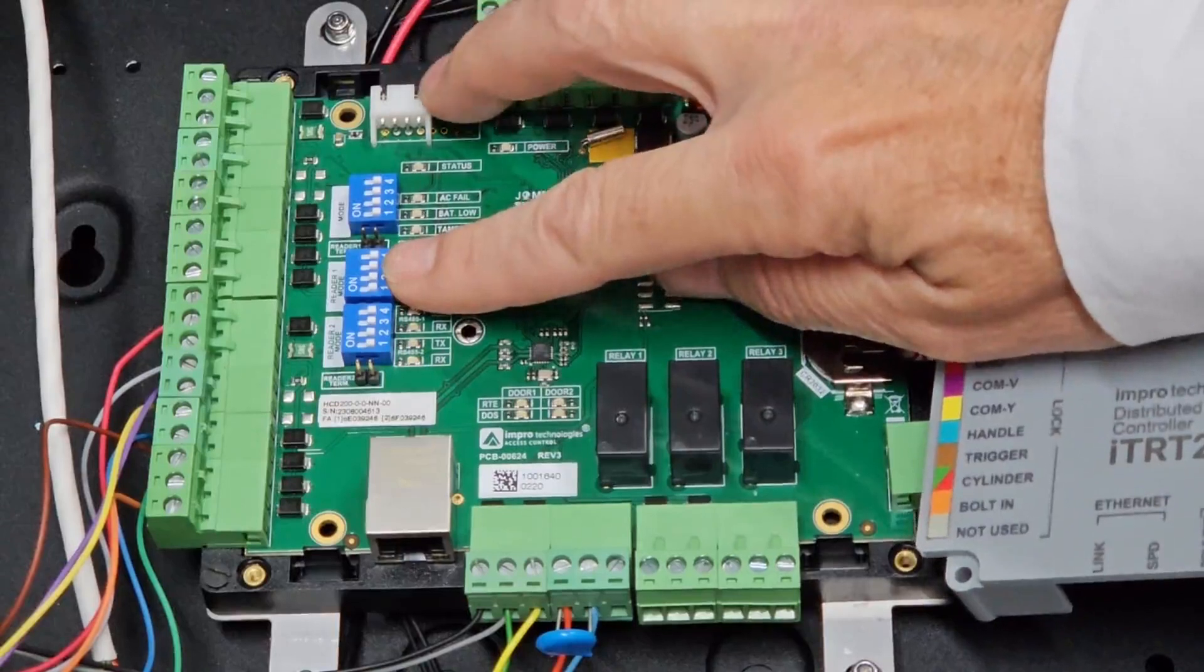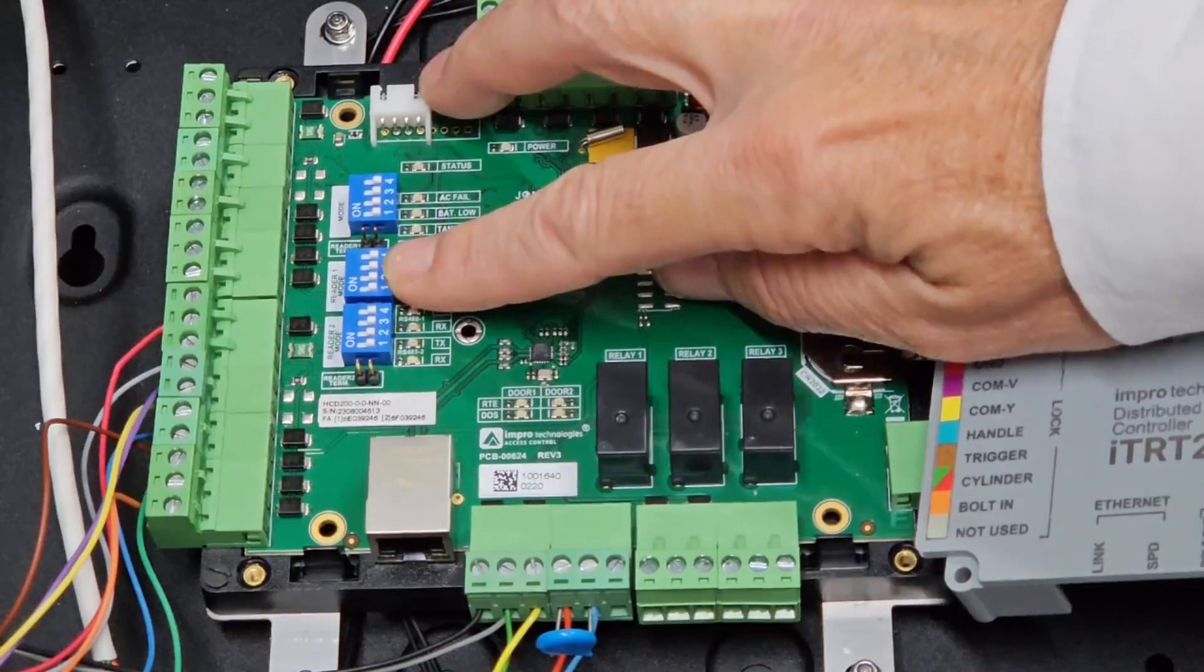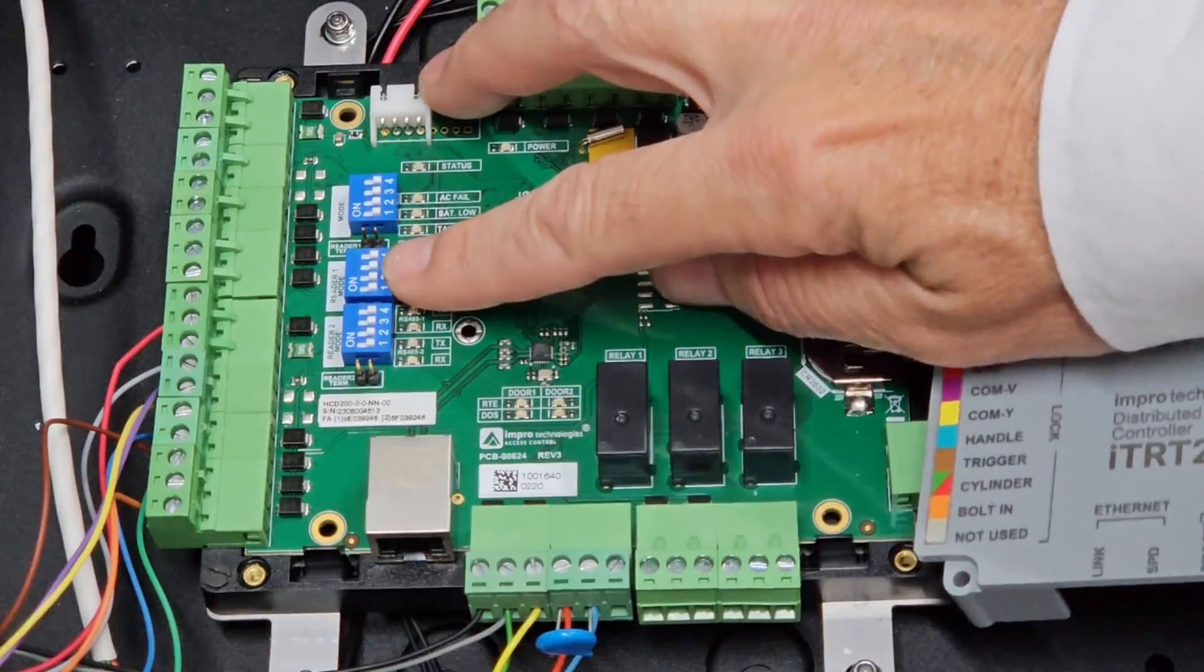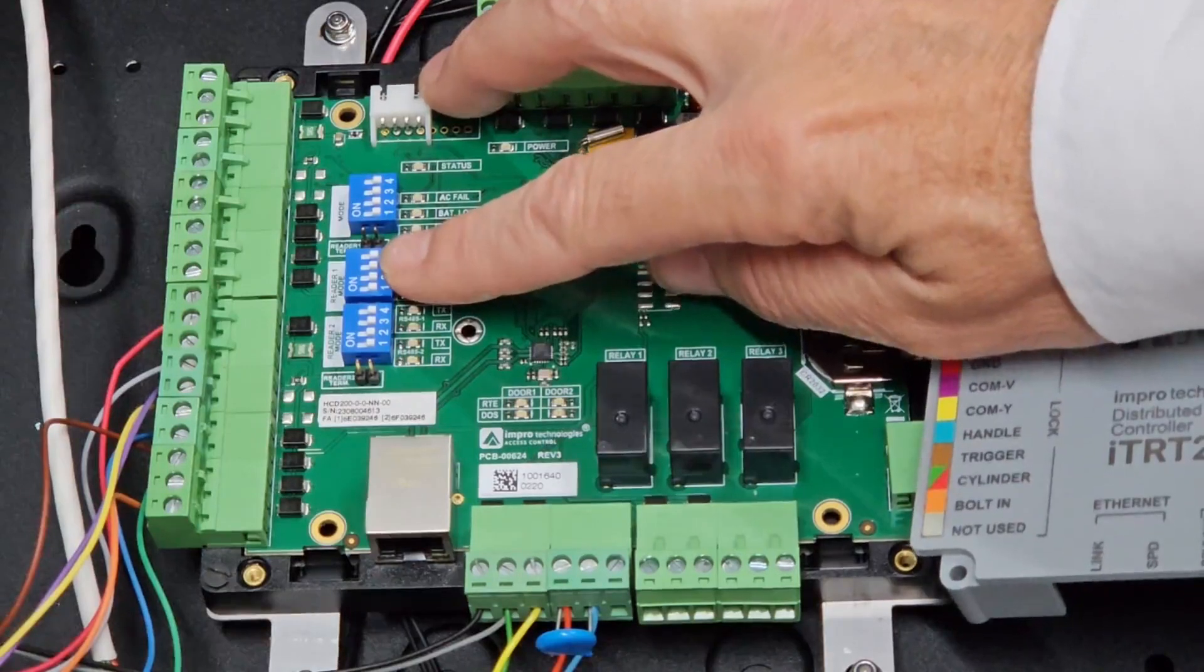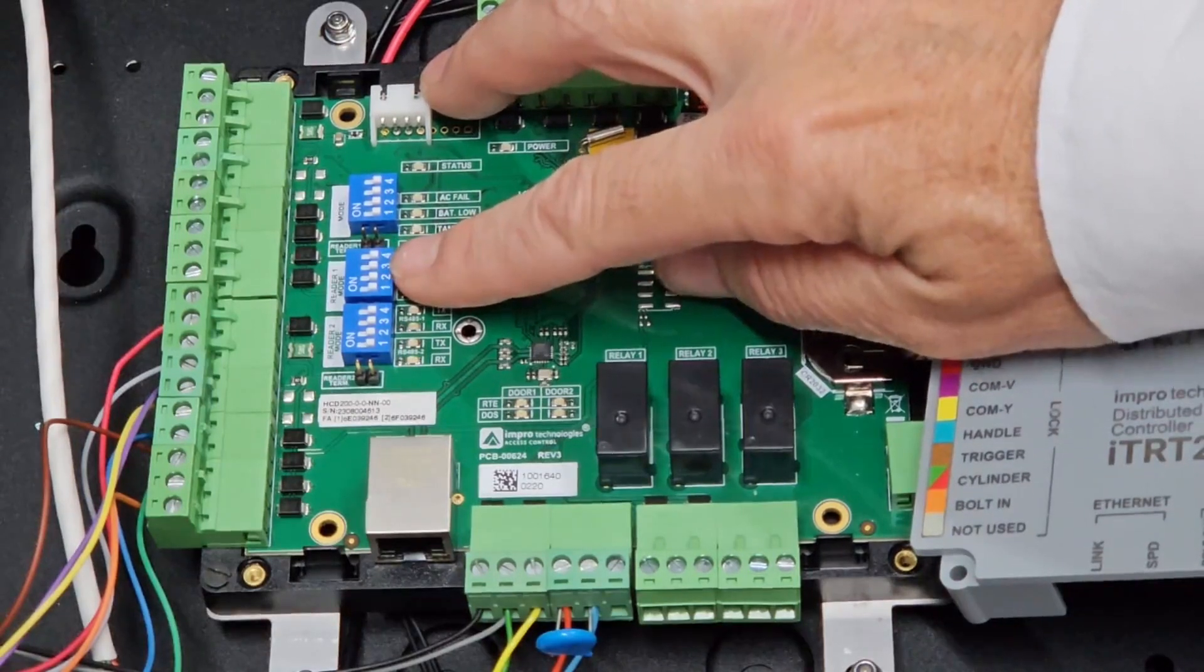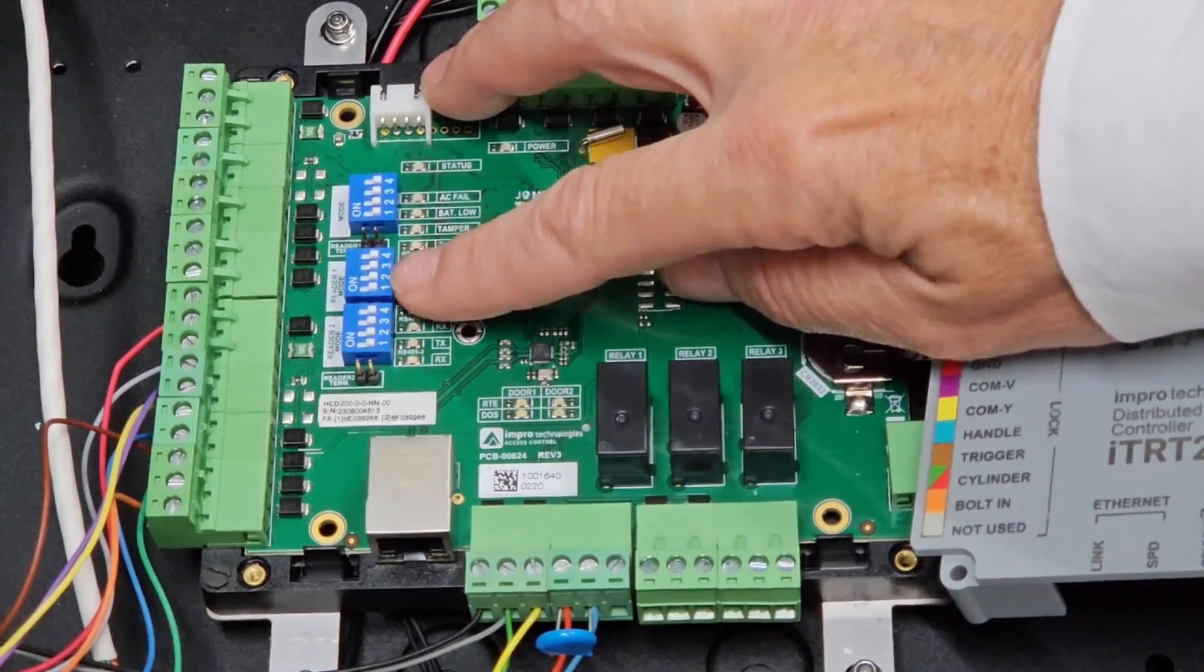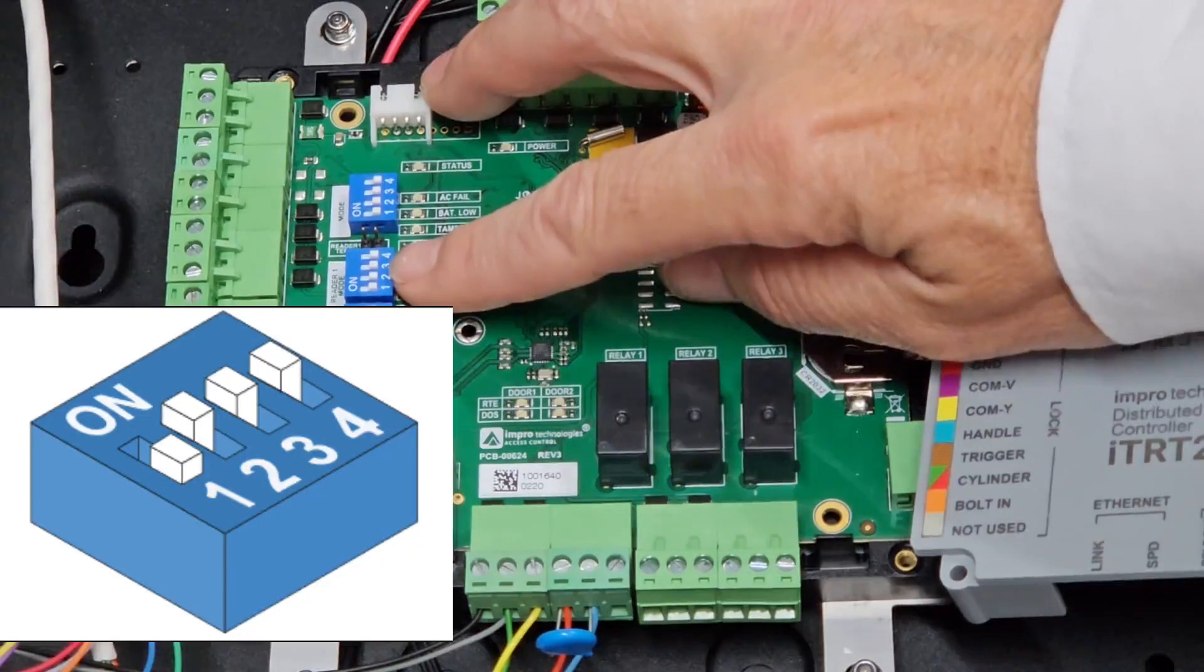This middle set of switches. Reader 1 switch should be set for the correct reader option. In the case of this installation, we need to set this to OSDP, which is 0111. That is all switches on, except the first one.